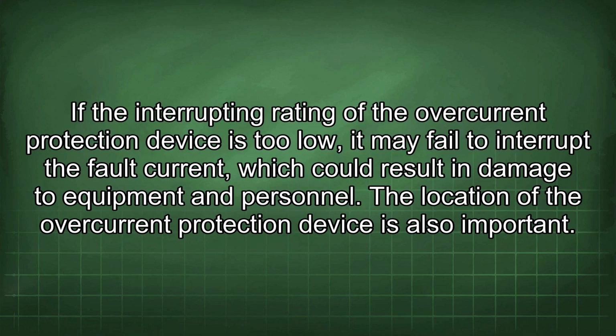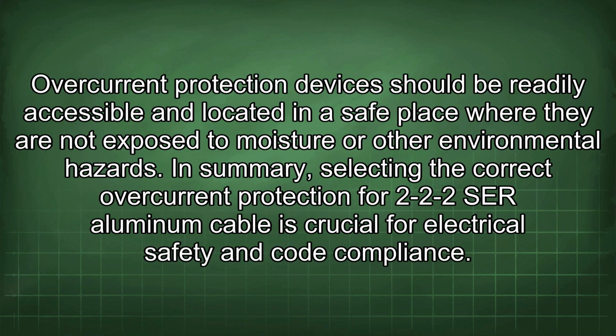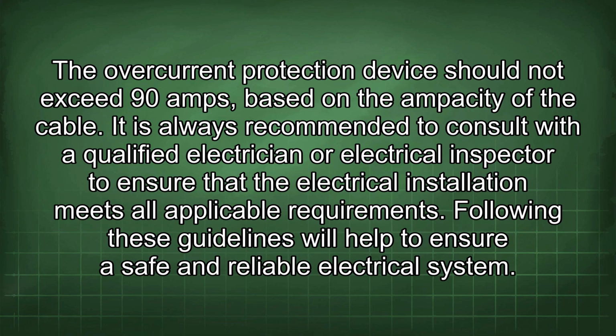The location of the overcurrent protection device is also important. Overcurrent protection devices should be readily accessible and located in a safe place where they are not exposed to moisture or other environmental hazards. In summary, selecting the correct overcurrent protection for 2-2-2 SER aluminum cable is crucial for electrical safety and code compliance. The overcurrent protection device should not exceed 90 amps, based on the ampacity of the cable. It is always recommended to consult with a qualified electrician or electrical inspector to ensure that the electrical installation meets all applicable requirements. Following these guidelines will help to ensure a safe and reliable electrical system.